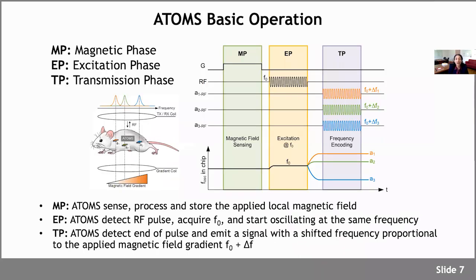So we tried to mimic different phases that MRI systems have in our system. At the first phase, which we call the magnetic phase, the chips measure the magnetic field. Then we have the second phase, the excitation phase, where we send a reference RF frequency at F0 to the chips, so that all the chips lock to the same frequency. We have a PLL on chip, as I will show, and all of them will lock to this frequency.